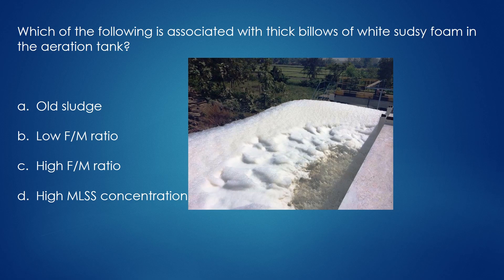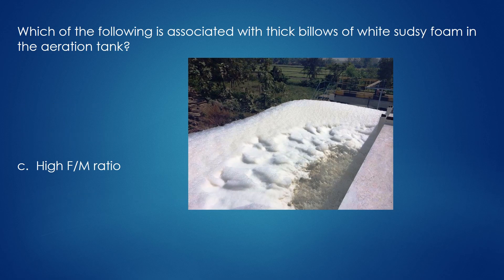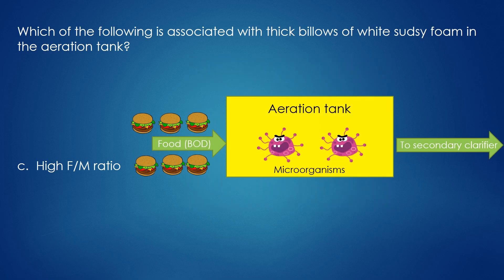Which of the following is associated with thick billows of white sudsy foam in the aeration tank? High FM ratio. Thick billows of white sudsy foam in the aeration tank is encountered during the startup of a plant when the FM ratio is high. During startup, there aren't a lot of microorganisms inside the aeration tank, but there's plenty of food or BOD coming in. As a result of this imbalance, there aren't enough microorganisms to eat the available food, which ultimately leads to foaming.